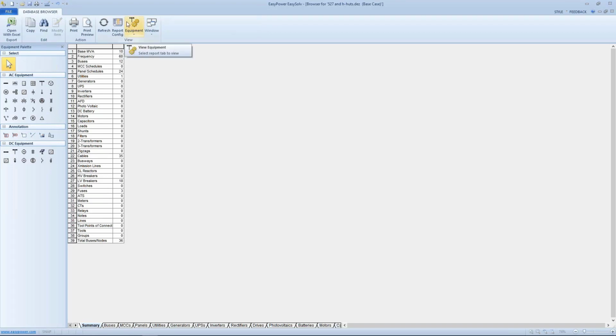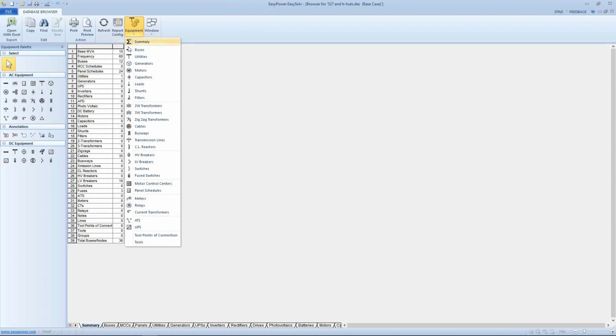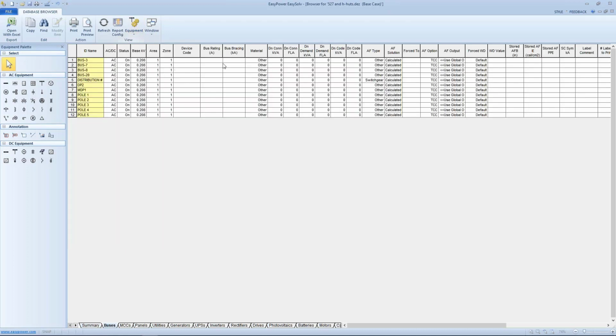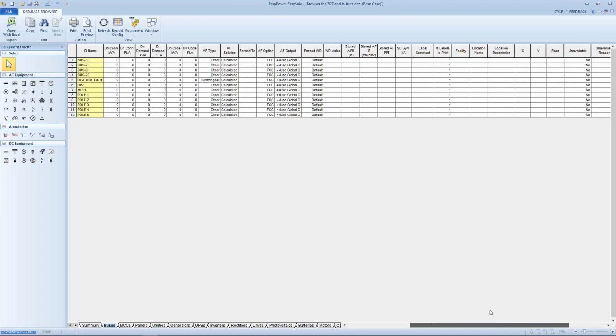If I go up and look in the equipment summary, I can group the buses together, and this shows me the data that's been entered for each one of these buses. The first thing that I notice is that none of the buses have a capacity rating, and none have a bracing rating. This is the data that's required for equipment duty calculations by the tool. Rather than beat this into the ground, my point is the tool does the equipment duty calculation automatically, and you're wasting value by not putting values in here for it to be able to compare.